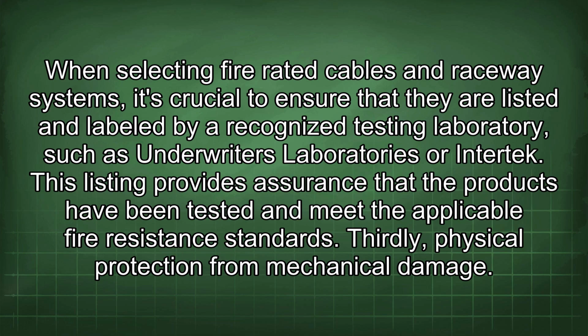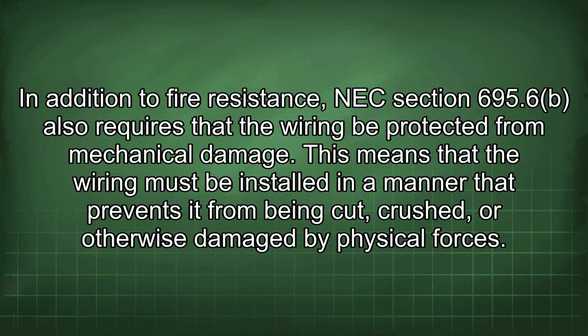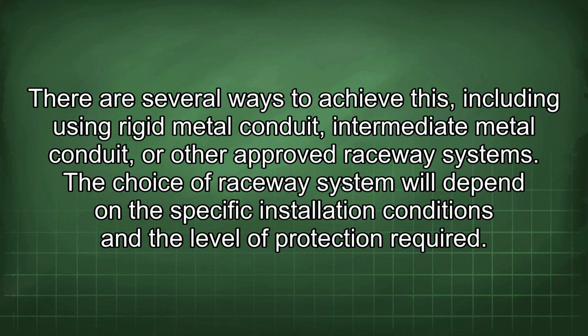Thirdly, physical protection from mechanical damage. In addition to fire resistance, NEC section 695.6 also requires that the wiring be protected from mechanical damage. This means that the wiring must be installed in a manner that prevents it from being cut, crushed, or otherwise damaged by physical forces.